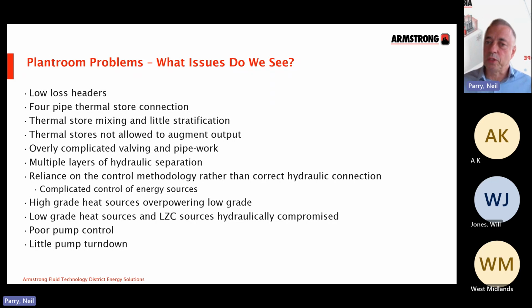Multiple layers of thermal stratification or hydraulic stratification, where you're losing efficiency, and of course you're adding in additional pumps each time you have hydraulic separation. A reliance on the control methodology to make things lead, and what tends to happen when you do that, the moment a more powerful energy source comes on stream, it tends to overpower the weaker source. So even if you've made it in the control methodology lead, it can be taken out of the equation once the bigger sources come online. And then, of course, as I mentioned, poor pump control and little pump turn down.